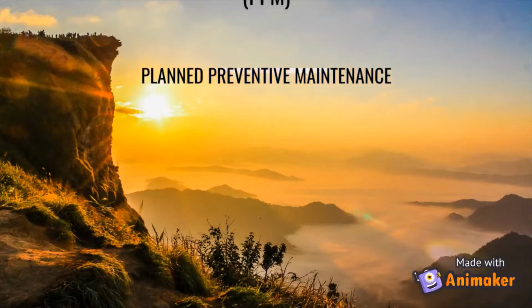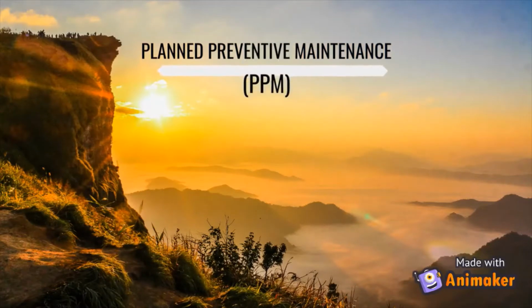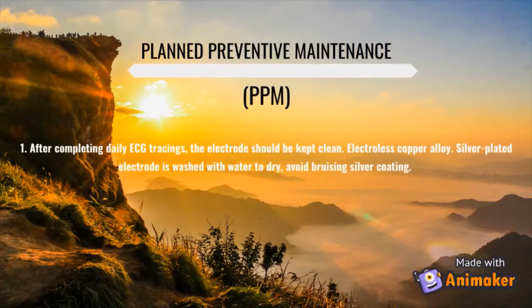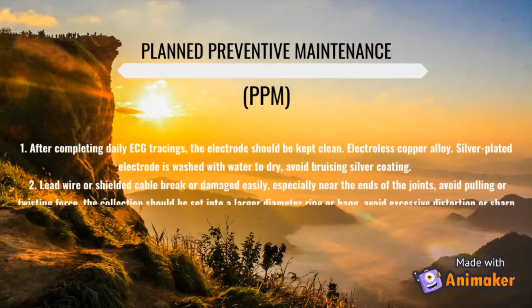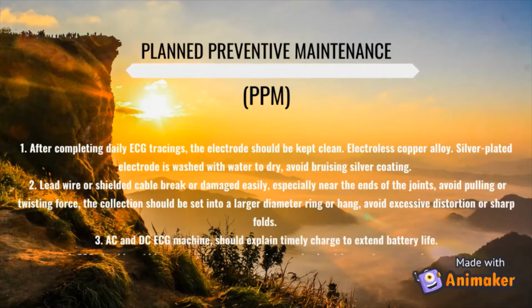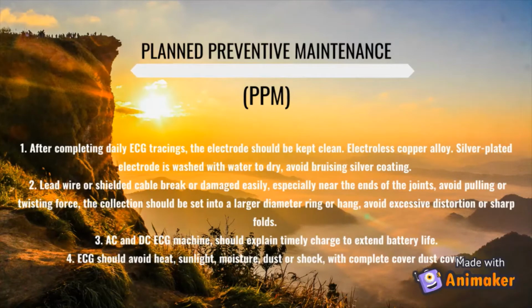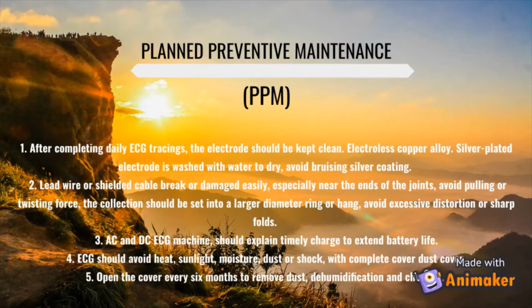Planned preventive maintenance: after completing daily ECG tracing, the electrode should be kept clean. The electroless copper alloy silver-plated electrode is washed with water and dried. Avoid bruising the silver coating. Lead wire or shielded cable breaks or is damaged easily, especially near the ends of the joints. Avoid pulling or twisting force. The connection should be set into a larger diameter ring or hung. Avoid excessive distortion or sharp folds.